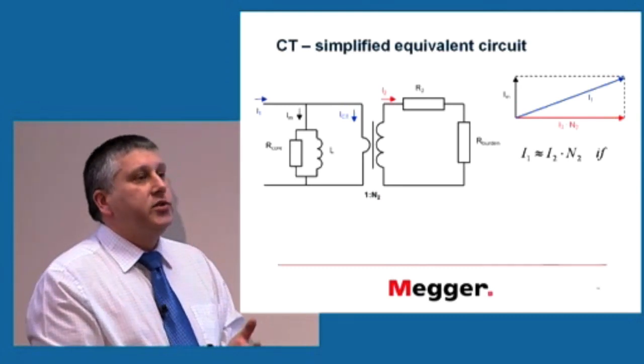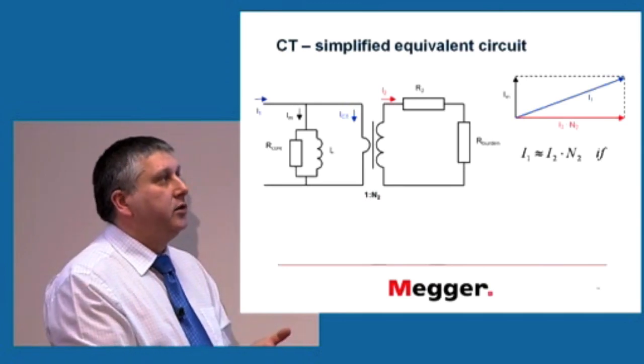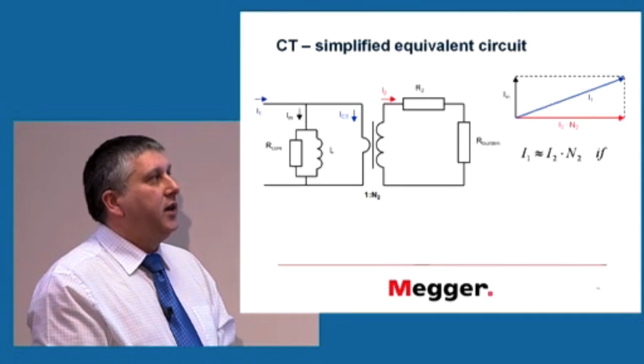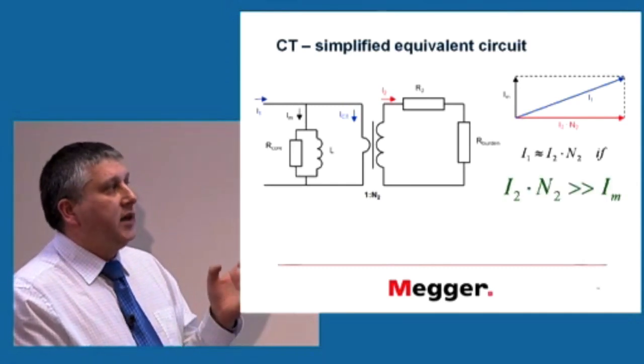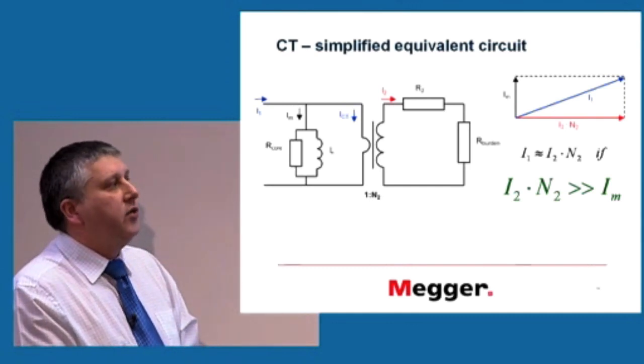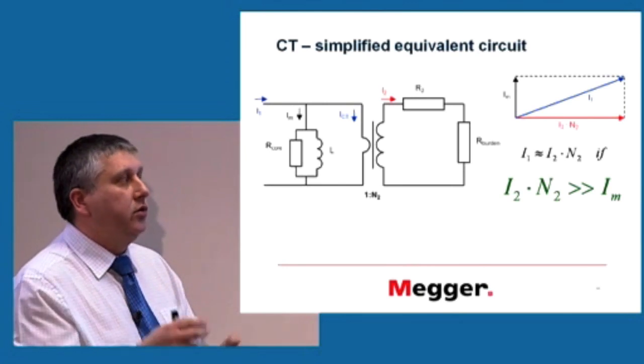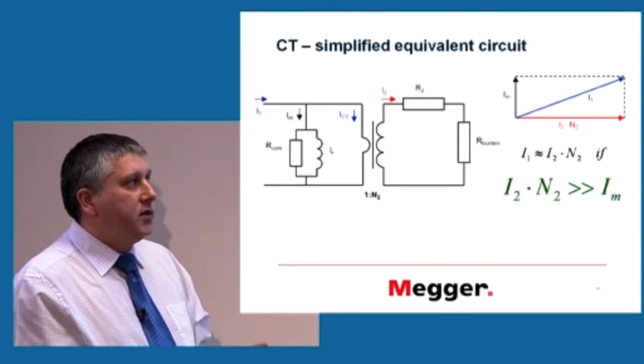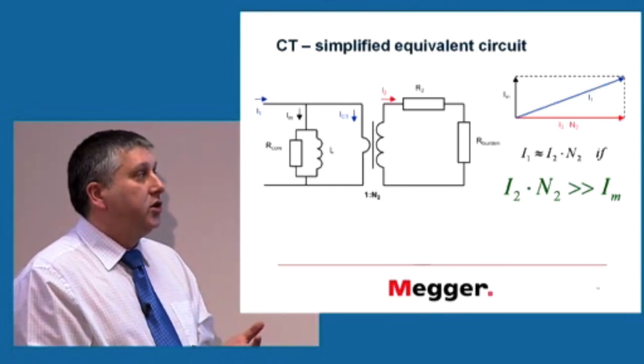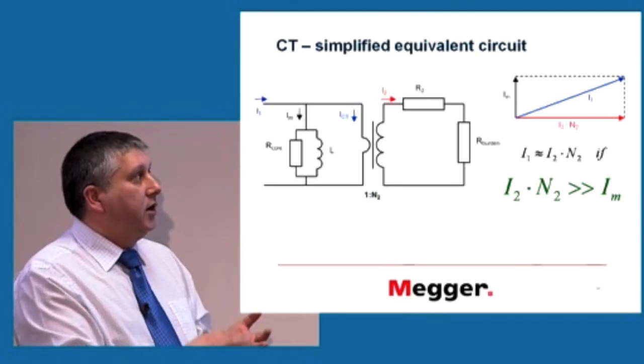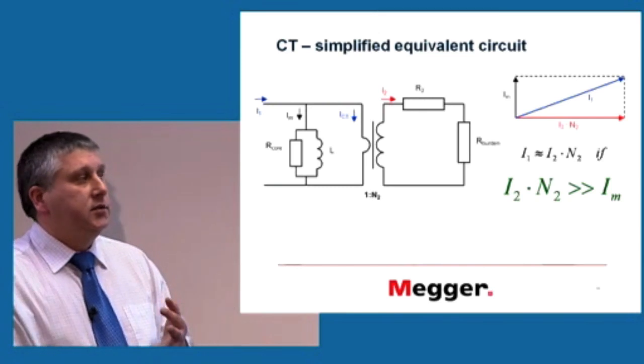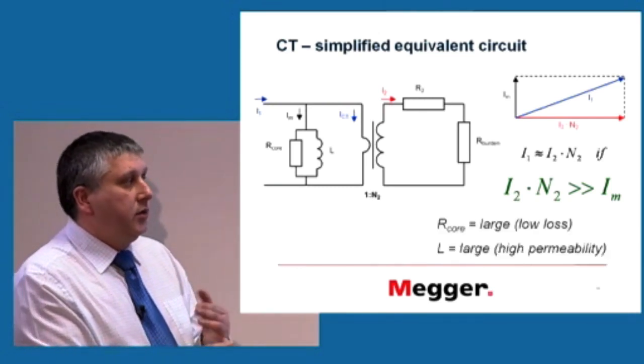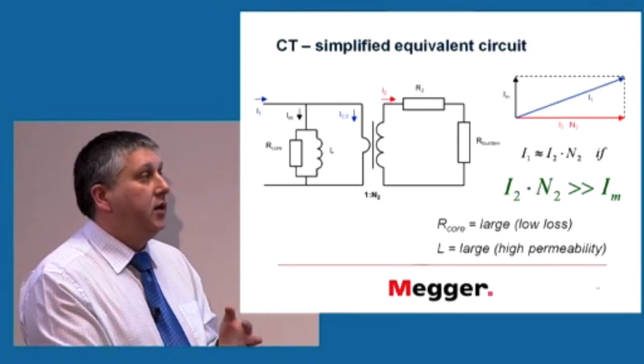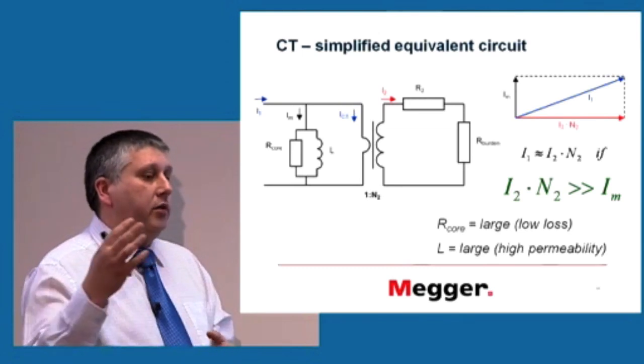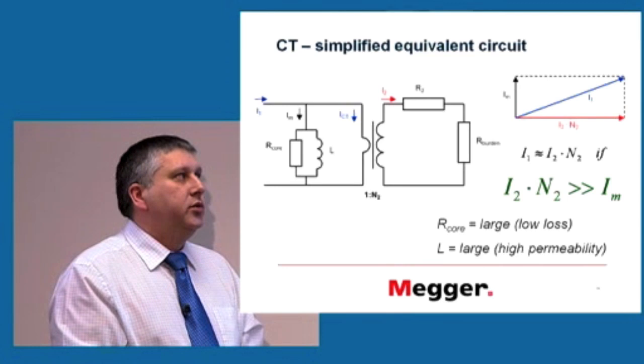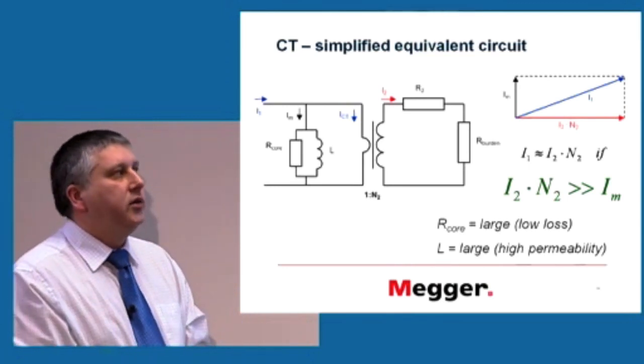So our aim is to relate our secondary current to the primary current. These would be almost equal to each other if our magnetization current is much smaller than our secondary current transferred to the primary, or the main current, as it were. To achieve this, we need the impedance of our resistor and our coil to be much larger than everything else - meaning a low loss core and very high permeability. Then we get the condition where our secondary current times the number of turns is almost equal to the primary. This just means errors, and the question is how big an error we can accept.